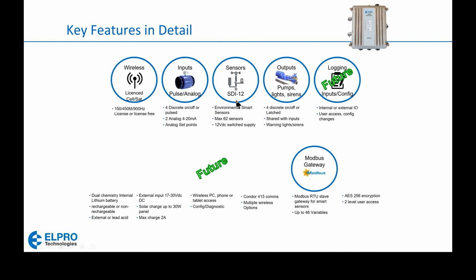Now in the SDI12 interface, up to 62 sensors can be connected to a single radio, and we provide a 12 volt DC switch supply for these SDI sensors. Then we have outputs. We have 4 discrete outputs, and they are latched outputs. So once you turn them on, they remain on until you turn them off. And the radio maintains the status of these outputs regardless of whether it is in sleep mode or whether it's actively powered on and taking samples.